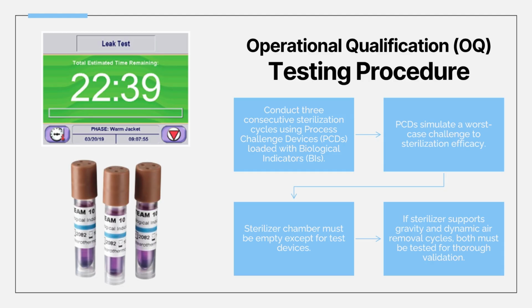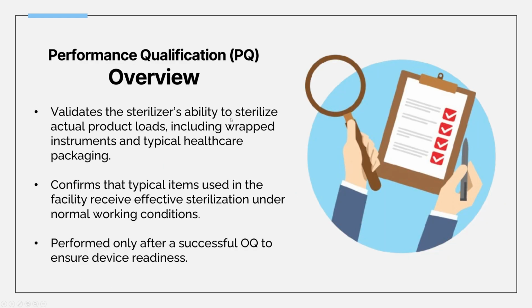Like I said earlier, the pressure, temperature, all of that, they have to meet the actual successful cycle parameters. Even if the machine were to say it's successful, if you find any discrepancies, then you have to immediately log that and let the technicians of the manufacturers know so they could fix it once more. So results are reviewed and verified before moving on to the next step.